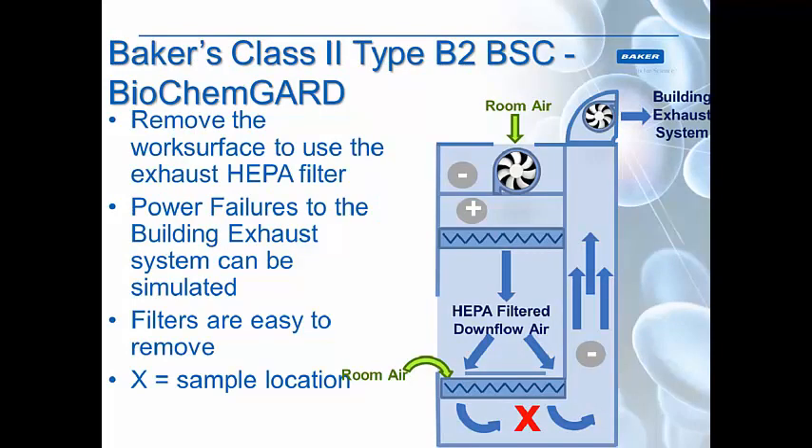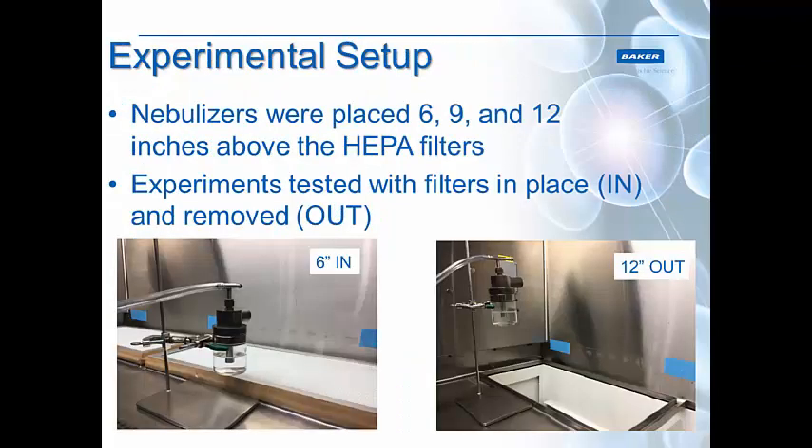First, we started with the Class 2 Type B2 biosafety cabinet. Using the Baker Class 2 Type B2 — the BioChemGARD — we know this style cabinet has a HEPA filter right below the work surface, and we're going to use this to our advantage. Because it is hooked up to the building's exhaust system, we also wanted to see if a power failure would jostle the DNA off of the HEPA filter. This style cabinet also has filters that are easy to remove, so we can reach our test samples very quickly. We placed the nebulizer either 6, 9, or 12 inches above the HEPA filter to see the distance-needed difference.